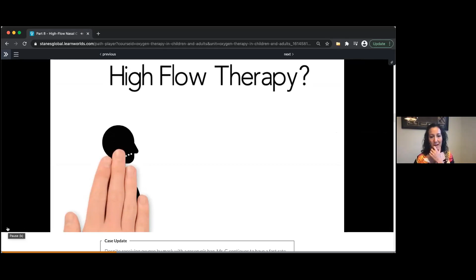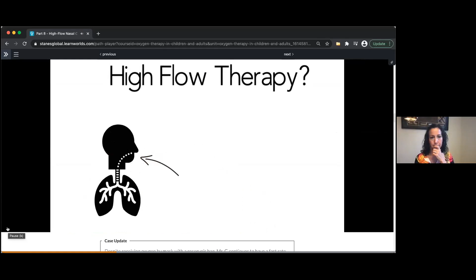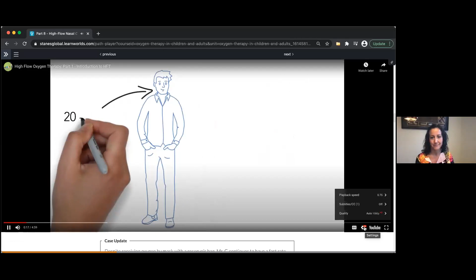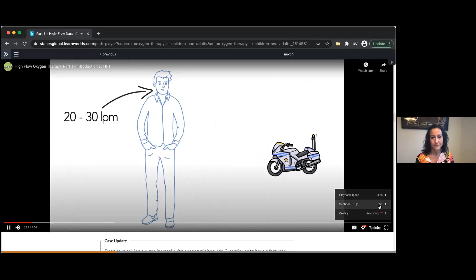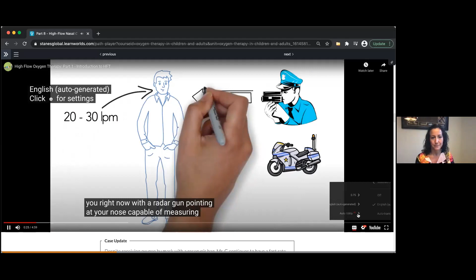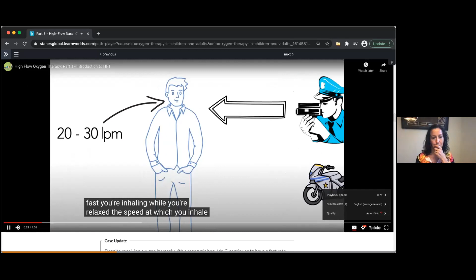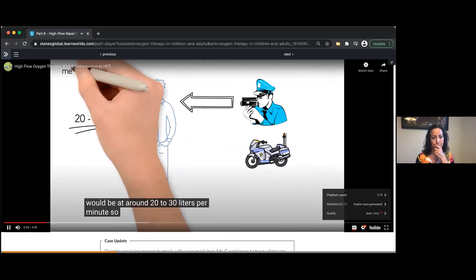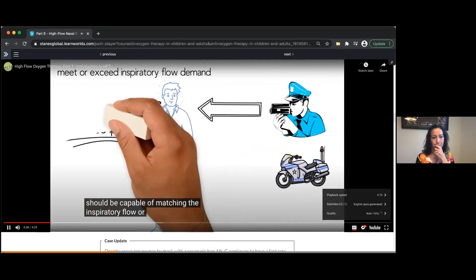What is high flow therapy? High flow therapy is when oxygen is being delivered to the patient at a flow rate that meets or exceeds their inspiratory flow demand. What does that mean? Well, did you know that at rest, the average adult will inhale at a speed of 20 to 30 liters per minute? In other words, if someone was standing next to you right now with a radar gun pointing at your nose, capable of measuring how fast you're inhaling while you're relaxed, the speed at which you inhale would be around 20 to 30 liters per minute. So high flow therapy should be capable of matching the inspiratory flow or even exceeding it.